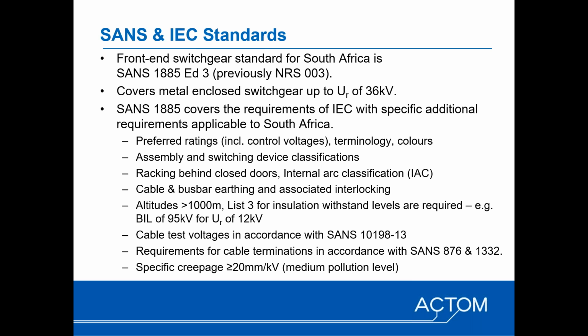So just briefly, why the need for front-end standards in South Africa, like SANS 1885? Well, firstly, it's important to point out that these are not contrary or in contradiction to the IEC. They are front-end to the IEC standards, and South Africa, being an IEC member country, has adopted the IEC standards without any modifications. However, amongst the users, there are preferences for certain design parameters, classifications, and then there are certain requirements which are unique, not entirely unique, but which are specific to South Africa.